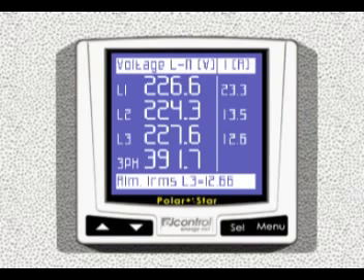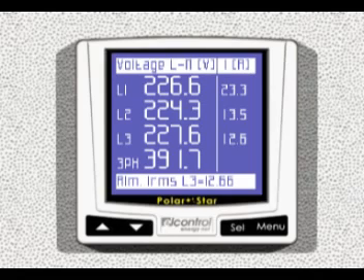In a bottom bar, visualization of occurred alarms. It's possible the setup of multiple alarm conditions. Alarms are notified on the screen, as well as stored into an alarm logger. If the meter is equipped with alarm relays option, it's possible to link the alarm condition to a relay.